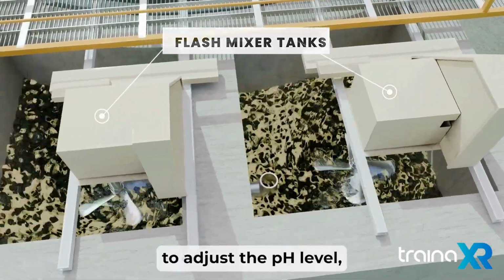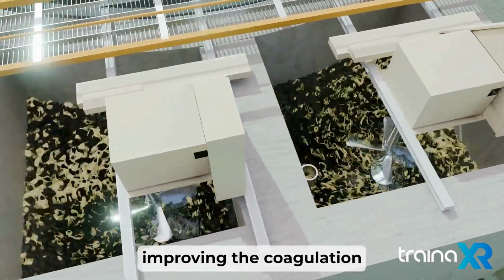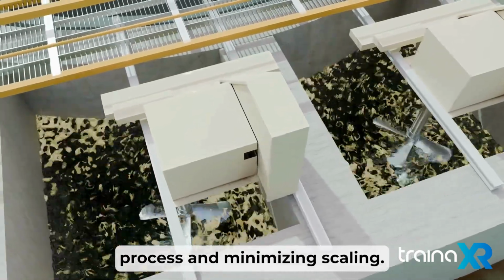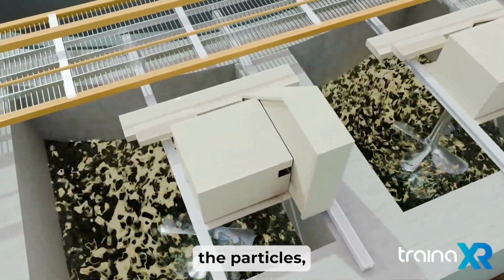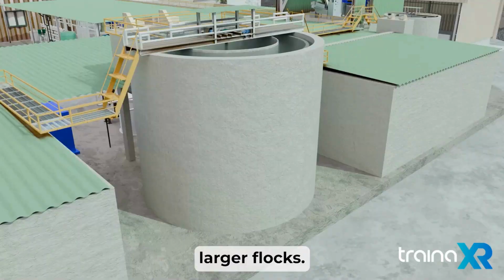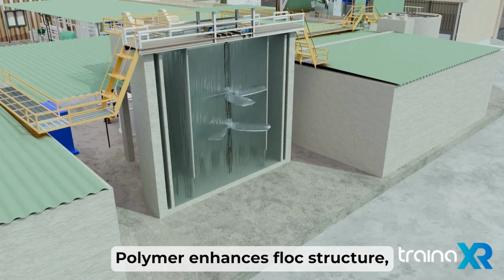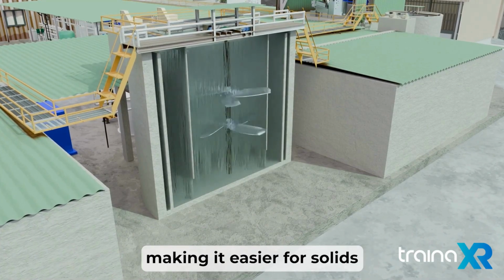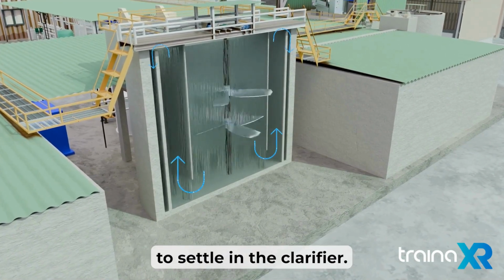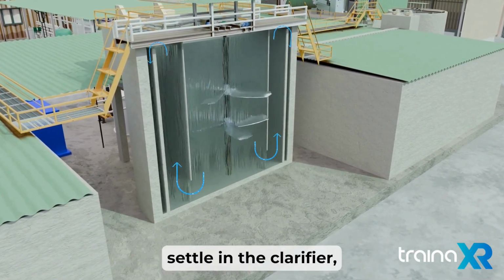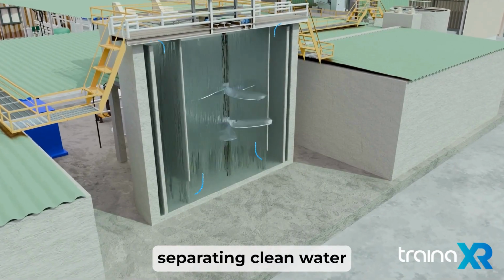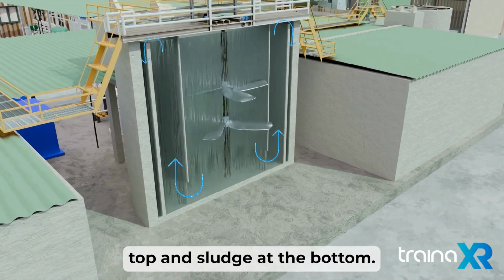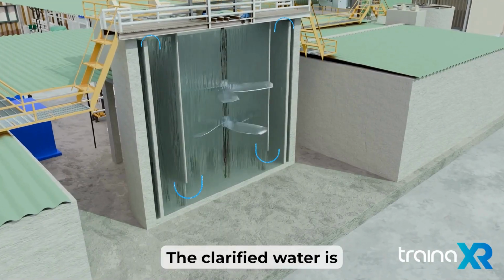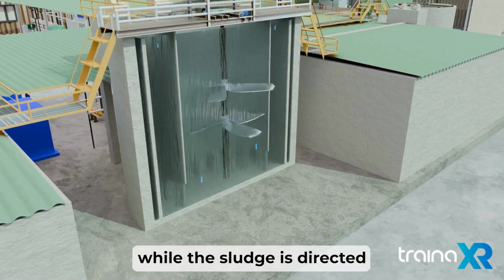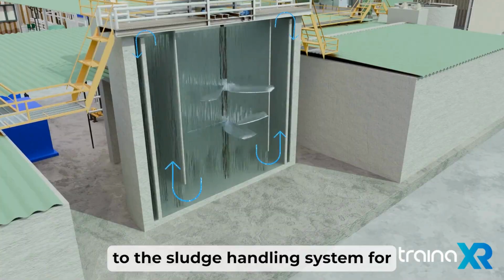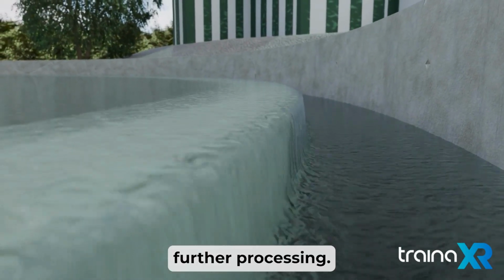Lime is added to adjust the pH level, improving the coagulation process and minimizing scaling. Coagulant destabilizes the particles, allowing them to form larger flocs. Polymer enhances floc structure, making it easier for solids to settle in the clarifier. The flocculated particles settle in the clarifier, separating clean water at the top and sludge at the bottom. The clarified water is sent to the next stage, while the sludge is directed to the sludge handling system for further processing.